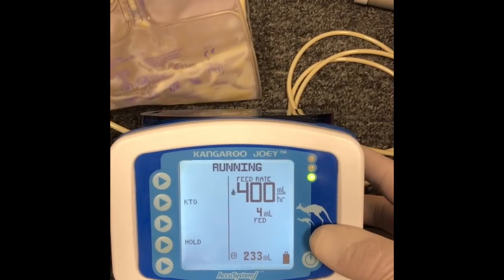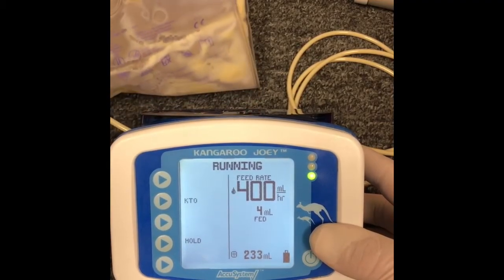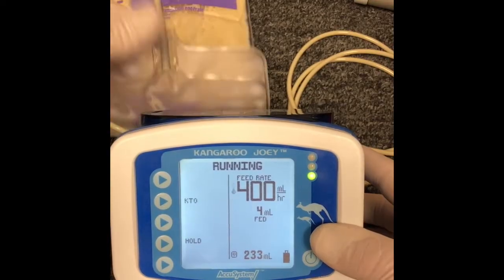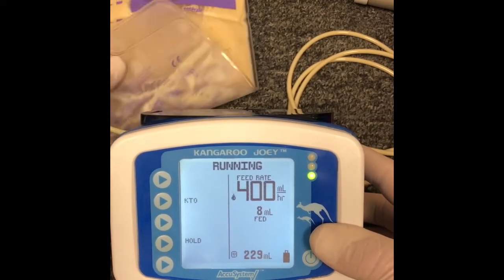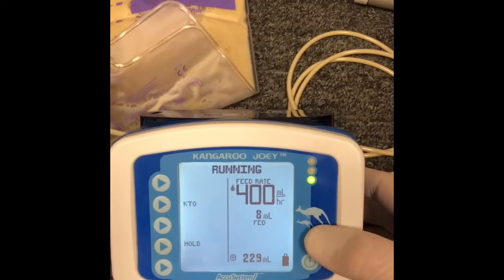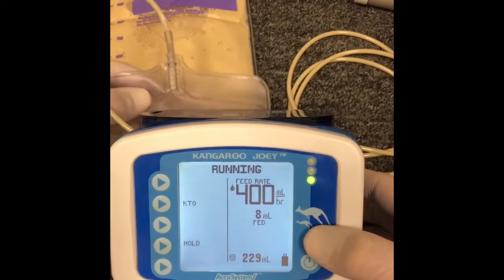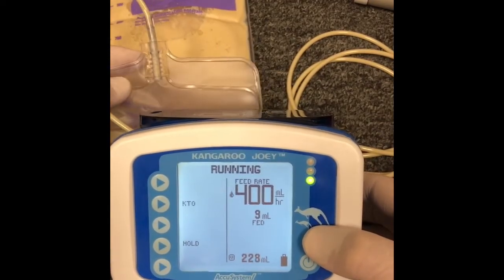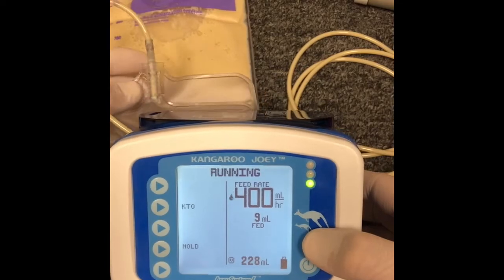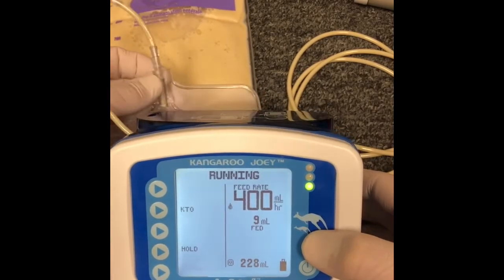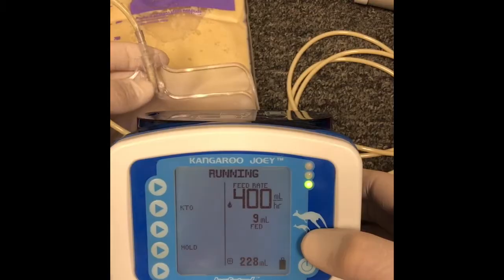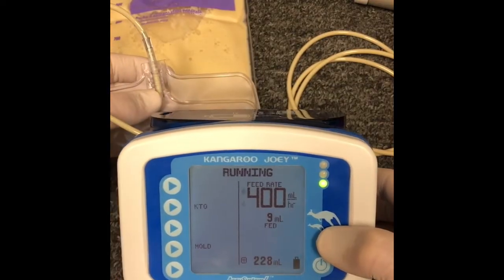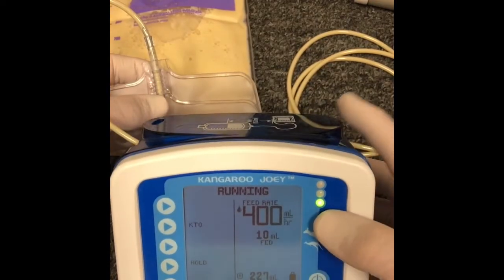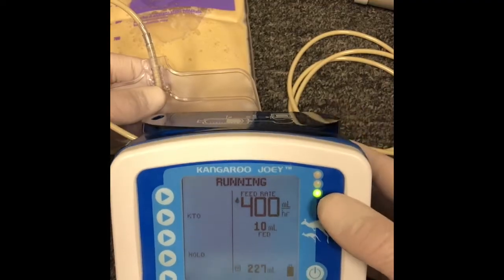And that's a normal alarm that it gets when it's empty. If it's programmed to give 500 milliliters and you only put 237 in the line, once it feeds all 237 and senses there's no more food going through the line, it will stop no matter what. That's designed to not pump air in there, so once the sensor detects there's no more food, it'll stop pumping.